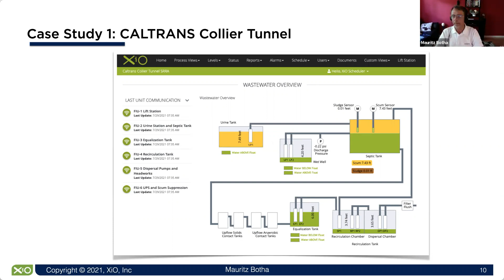The system also gives operators the ability to interact with each one of the devices, so they can change lead-lag settings - meaning if the level drops below a certain point, the first pump comes on, and the lag pump comes on later if the first one can't keep up. So we measure all kinds of efficiency. And one of the other benefits of providing a cloud-based service is we can aggregate all the information from the systems that we manage.